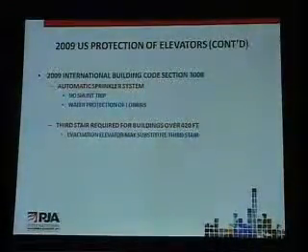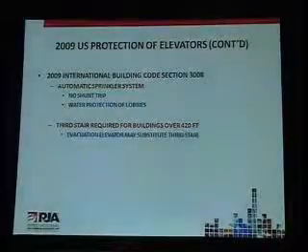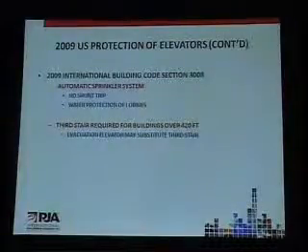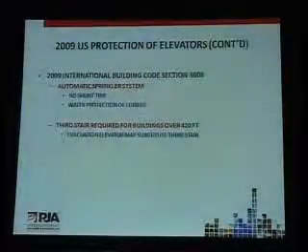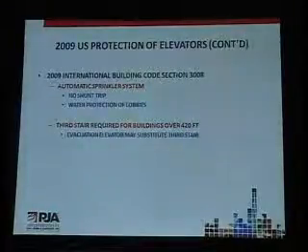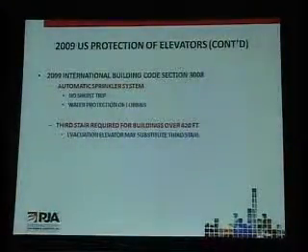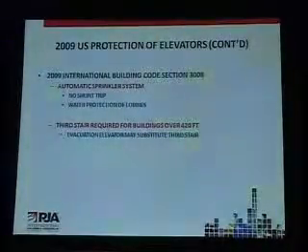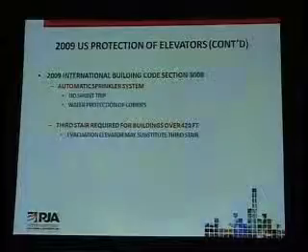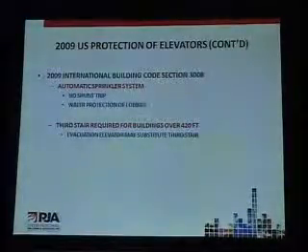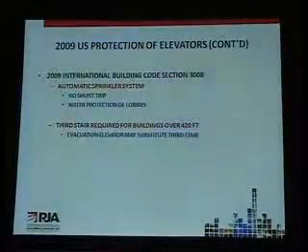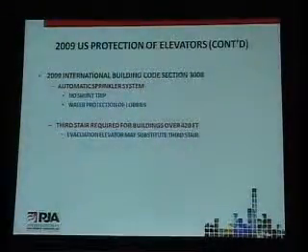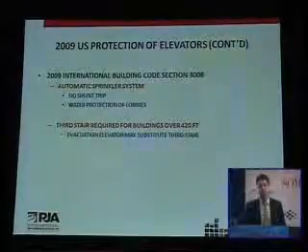Some other specific requirements relating to fire protection: in the International Building Code, high-rise buildings are required to be sprinkler protected throughout. When employing this type of evacuation system, there are some exceptions for sprinkler protection to make sure that water does not increase the risk of using these elevators during an event. So, for example, in the machine room, typically you're required to have a shunt trip. You're no longer required to have this shunt trip. In addition, something that we've seen in the Chinese standard way of protecting the vestibules is that water protection is required.